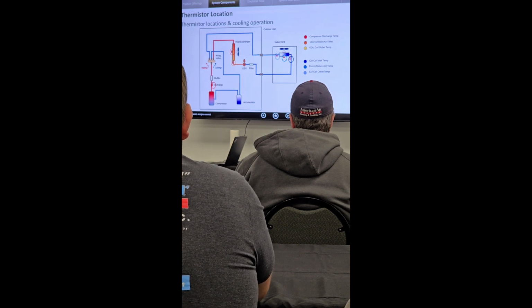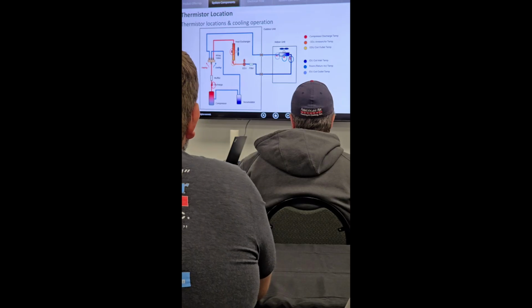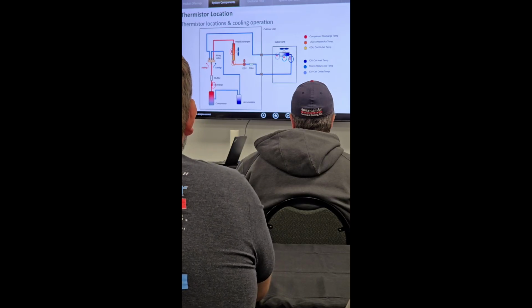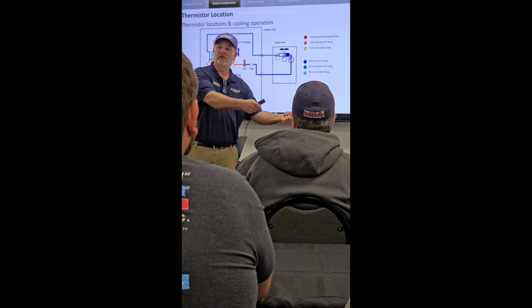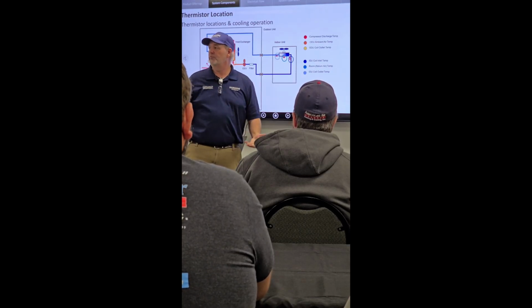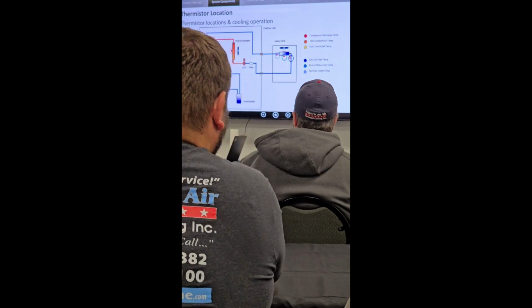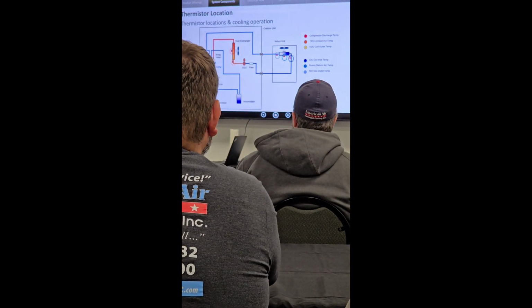Honestly, I get it on the phone, and I've had it with people who actually work for the company. They say the unit's not working, you run out there, and guess what? They didn't want to cut the line set, and thinking they were doing well, even though it's not behind the condenser, they shoved it up underneath the house, the whole rest of the 25 feet. But a loop is a loop, right? An oil trap is an oil trap, it's still the same scenario, so we have to straighten it out or cut it down.